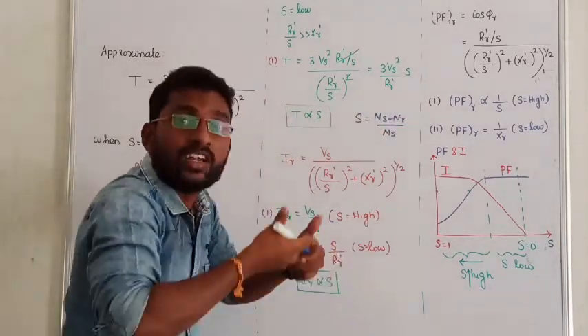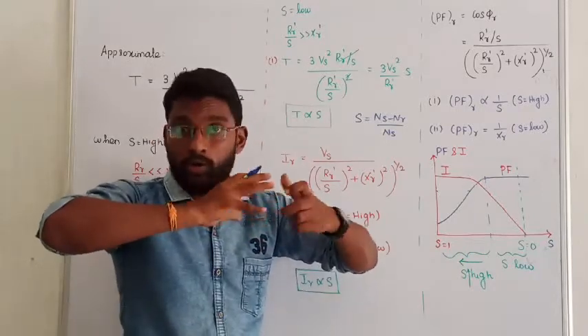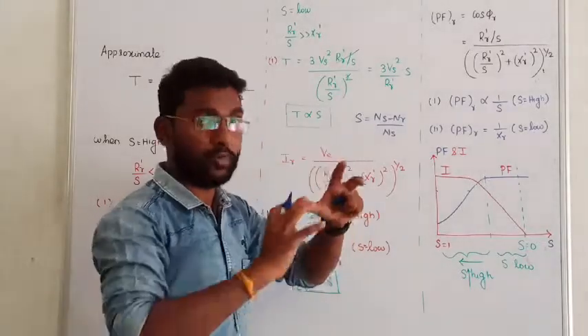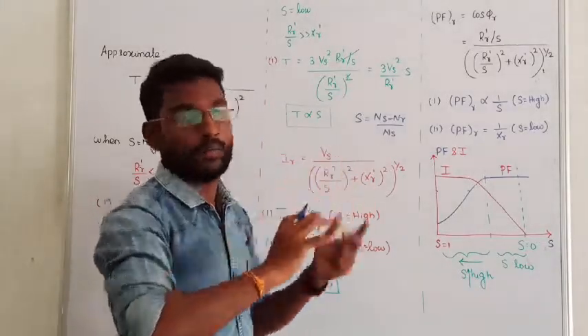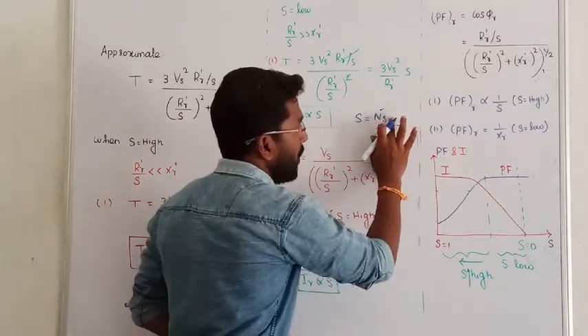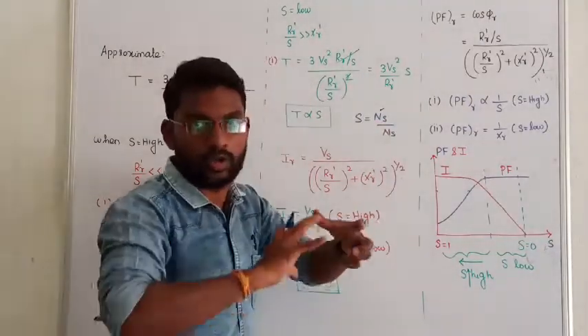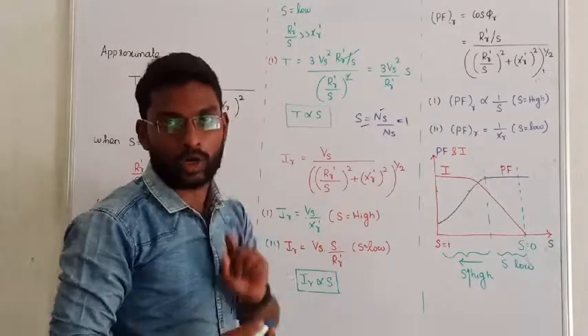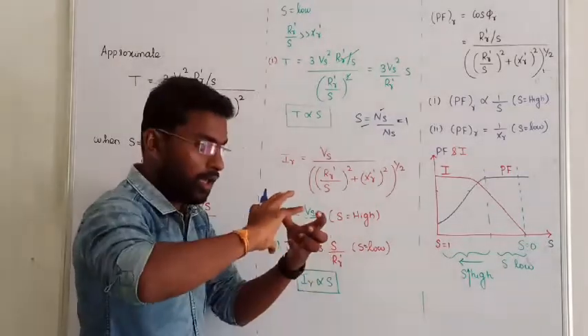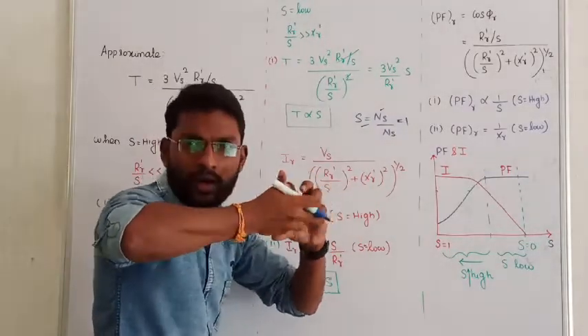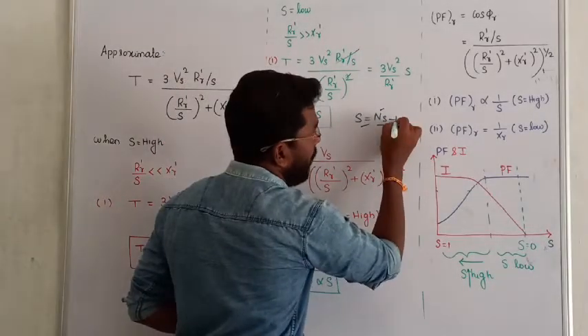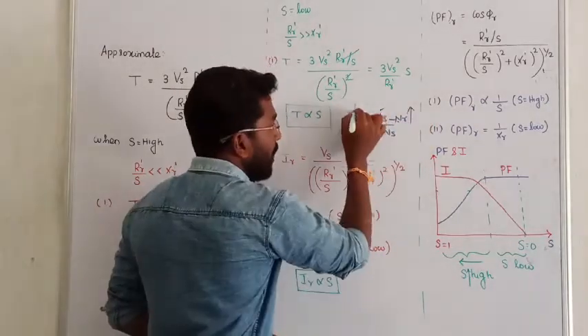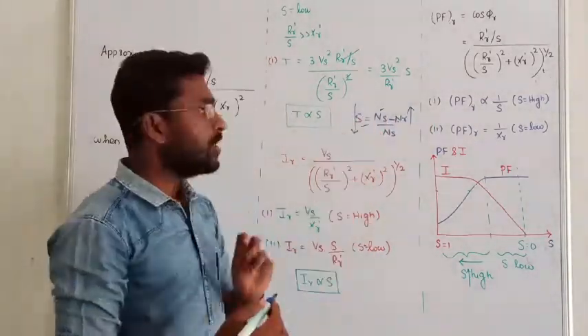When the moment we are starting the induction machine, the rotor speed is 0. The rotating magnetic field will be revolving, so the synchronous speed is established. But the rotor is stationary at start — rotor speed is 0. So I can say, when we are starting the induction machine, the slip value is going to be 1. The rotor slowly picks up speed from that point.